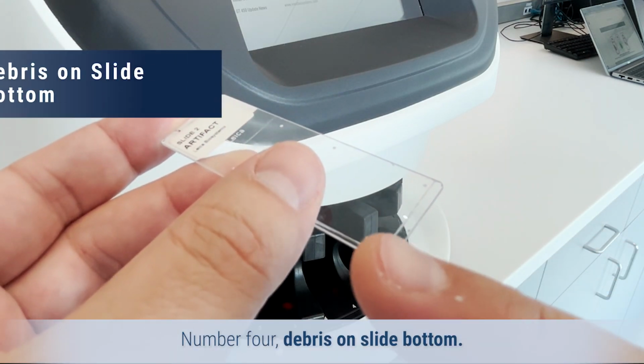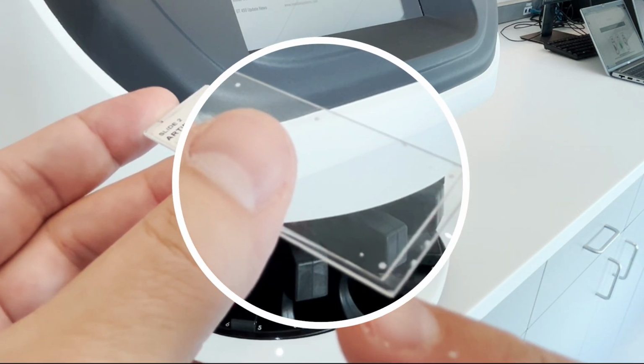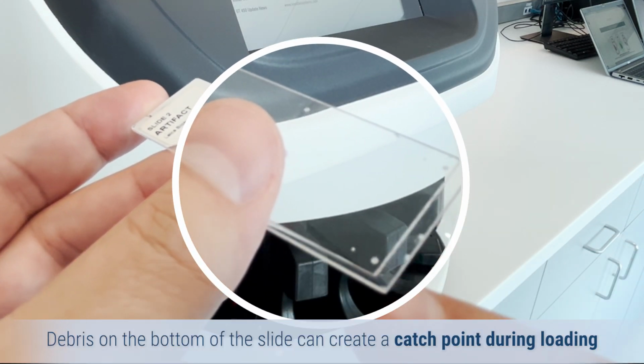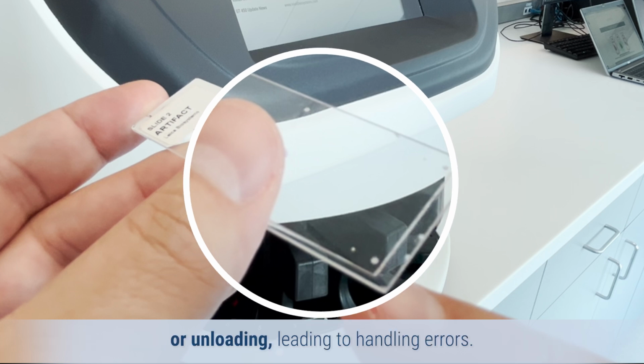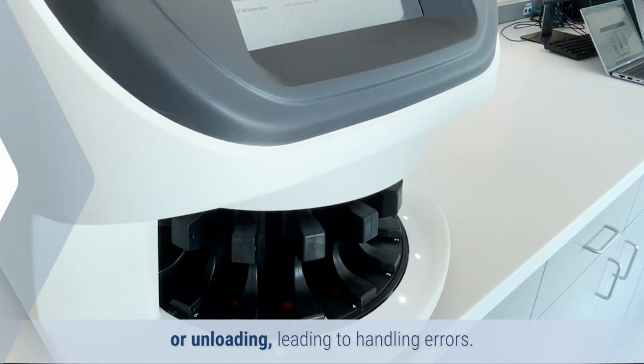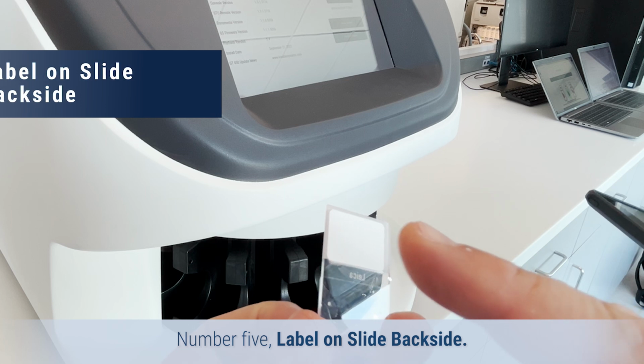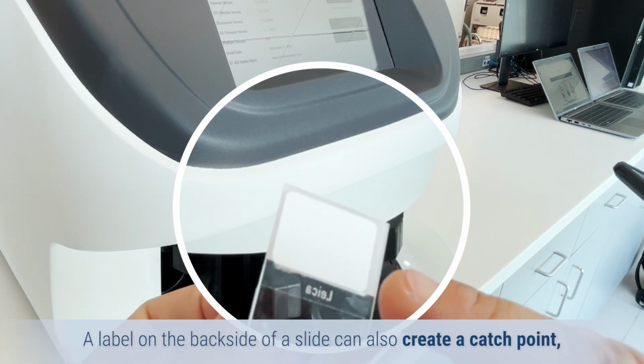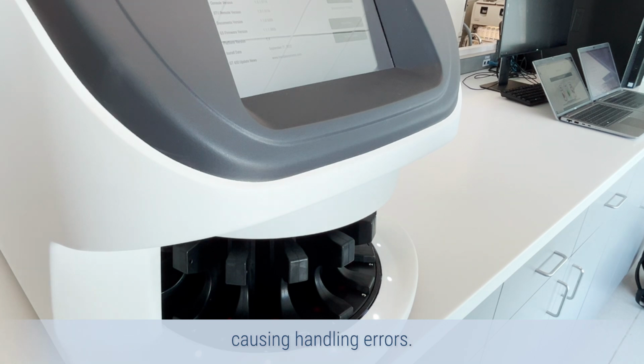Number 4, debris on slide bottom. Debris on the bottom of the slide can create a catch point during loading or unloading, leading to handling errors. Number 5, label on slide backside. A label on the backside of a slide can also create a catch point, causing handling errors.